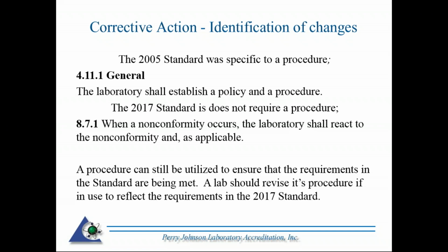To kick off the requirements under 8.7.1, when a nonconformance occurs, the laboratory shall react to the nonconformance as applicable. One thing I'd like to stress, though: if you're operating under a procedure and the procedure works, although not required, it can still be utilized. And to ensure that the requirements are being met, if you are going to transition with your procedure, I would recommend revising it to reflect the requirements of the 2017 standard.